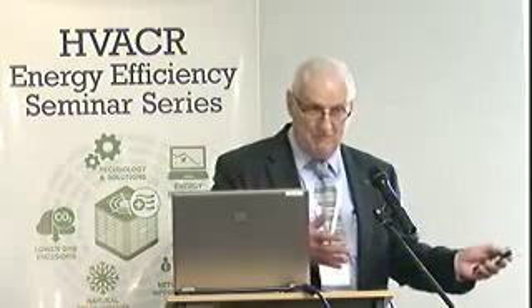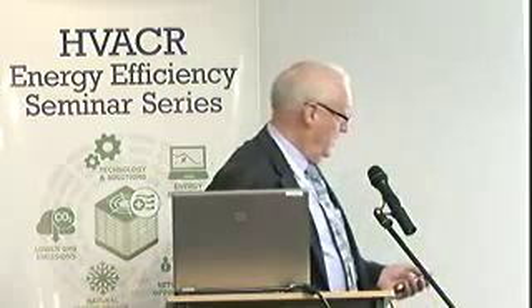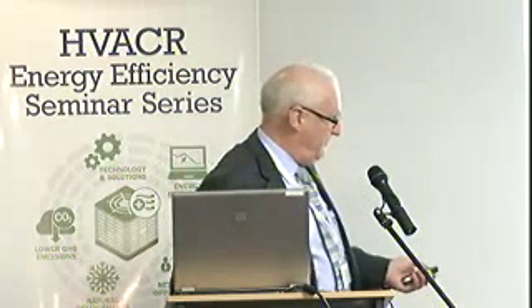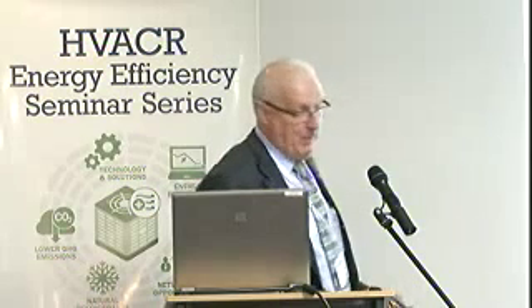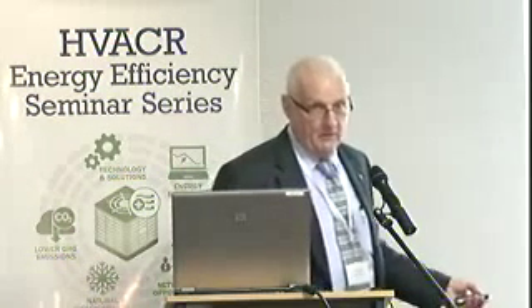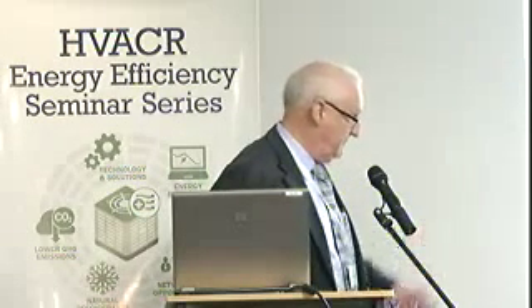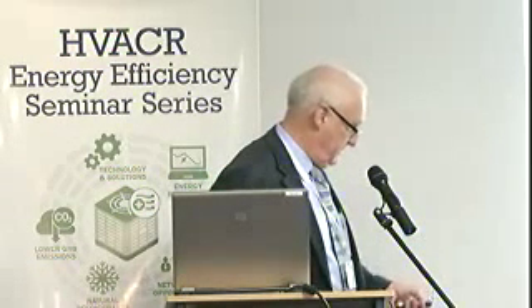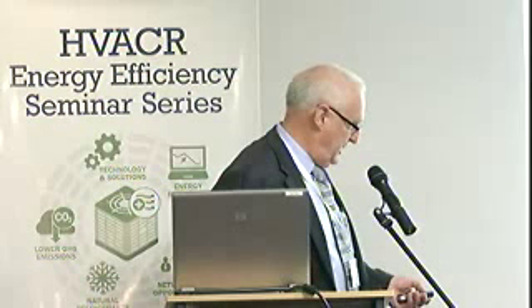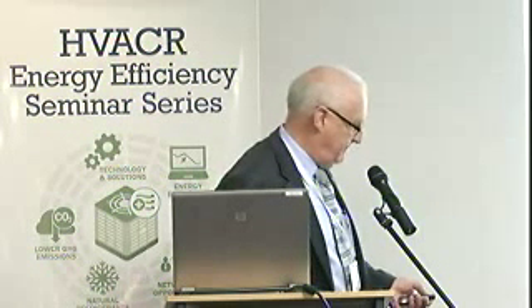And we saw an example of a site where it had that. Motor losses increased 25% with a 4% unbalanced voltage, as you can see down here. I've had to highlight with a pen on these because they were black and white. Now, the references for these are in the paper. So, as I said, you're very welcome to share this with any of you. So you can see here the 4%: we've got the motor heating increased by about 30%.